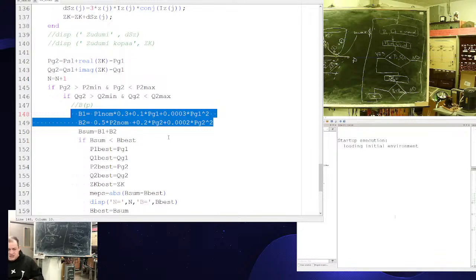In my case, it's from some old power plant. You will not get it as a ready-made polynomial. You will get a test table and a nice chart approximated with a polynomial. Take Excel and do it. It will be your job, with the test chart in the commissioning paper.